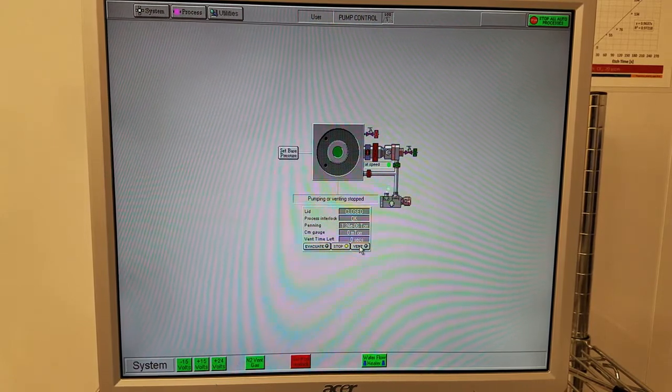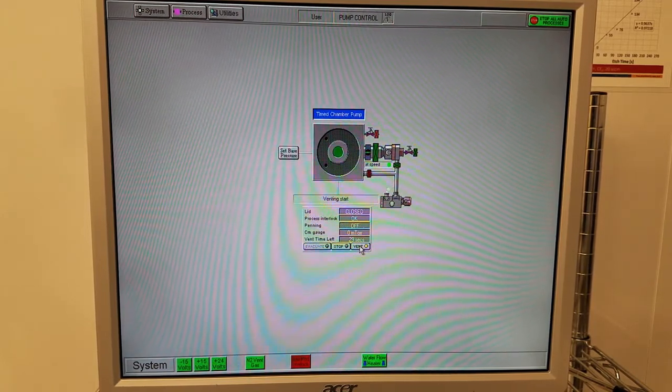Now we can start running our process. The tool is always kept under vacuum when not in use, so we need to vent it so we can load our sample. Click stop, vent, and wait until it finishes.